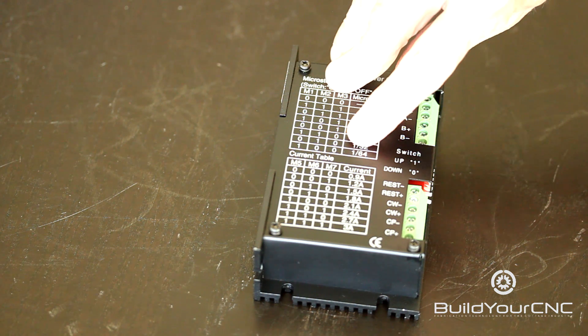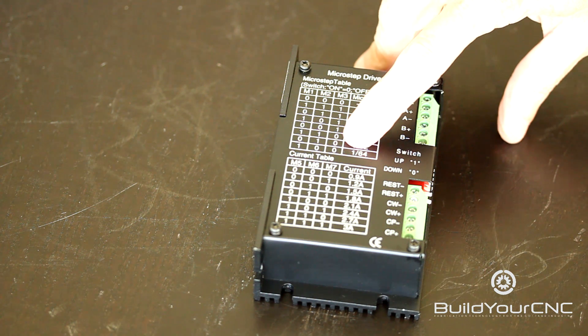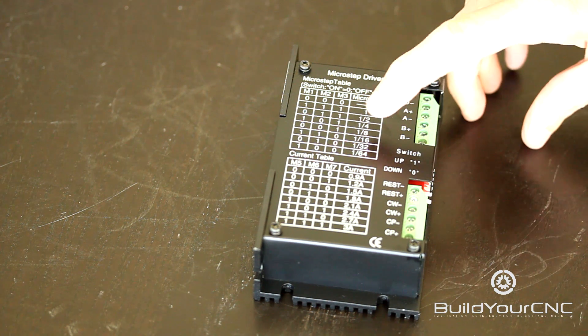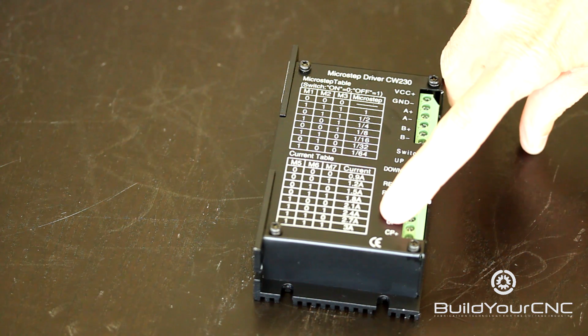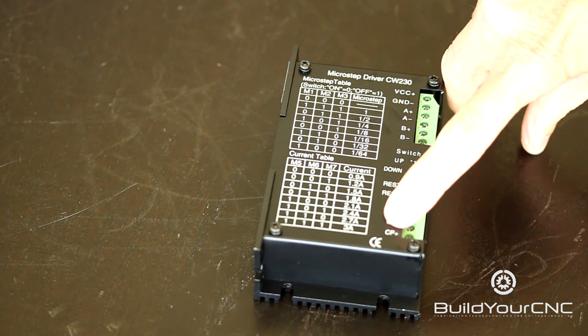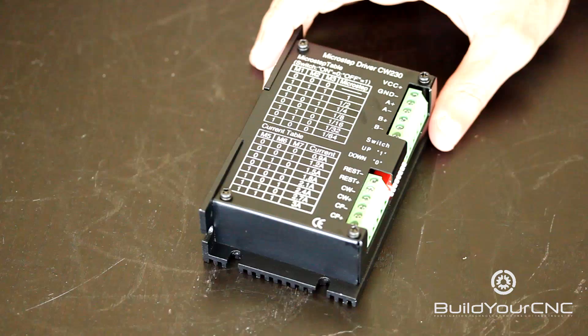The steps go from one full step all the way to 1/64ths, or 64 steps per full step. So on a motor that has 200 steps per revolution, you would need to send 12,800 pulses to the pulse terminals to achieve a full rotation.